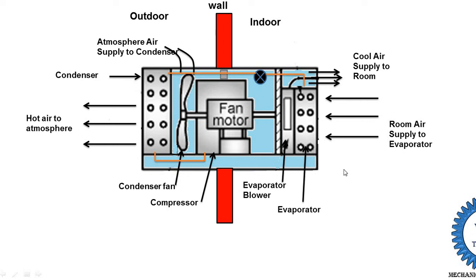The window air conditioning system is used for cooling small rooms with fewer occupants. There are certain disadvantages. First, the compressor is near the wall, creating noise inside the room. Second, it cannot be installed as a decorative unit because the condenser is part of the single unit, so it cannot be completely concealed inside the room. Third, it requires a certain space on the window — a perfect slot size is needed to fit the unit into the window.